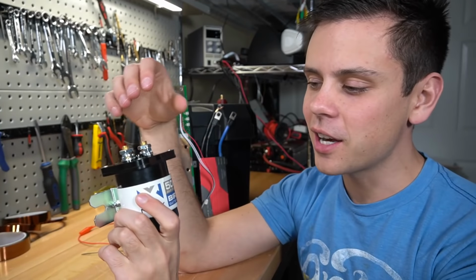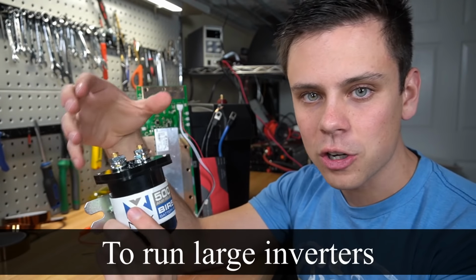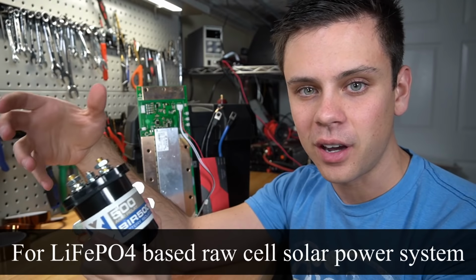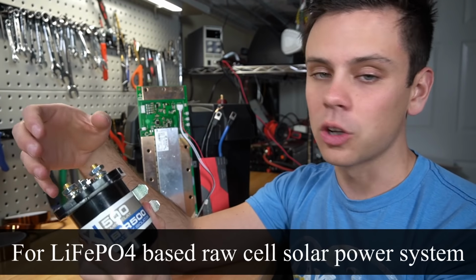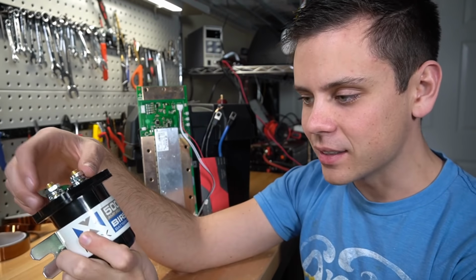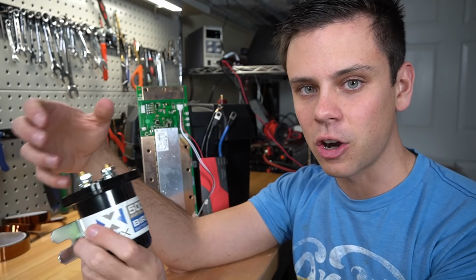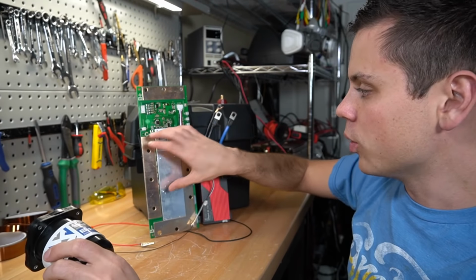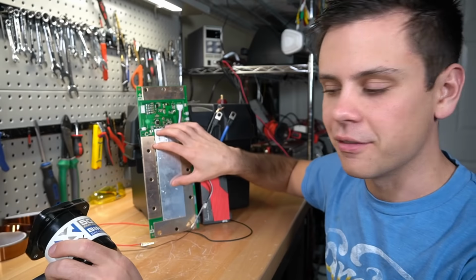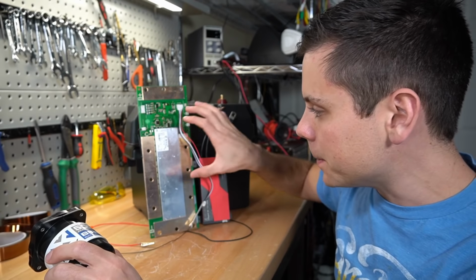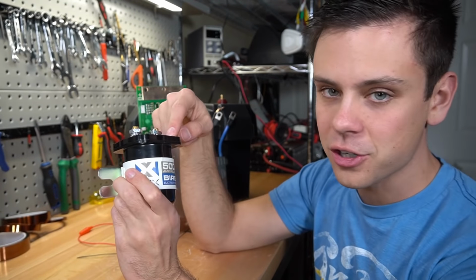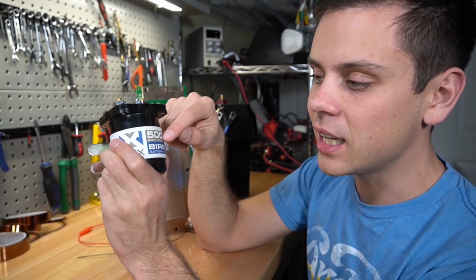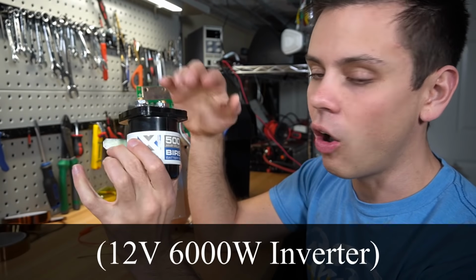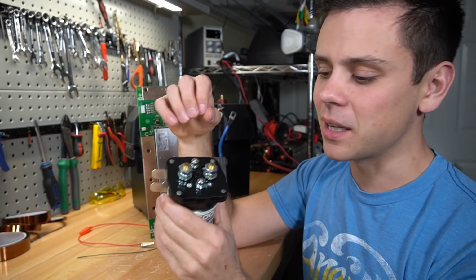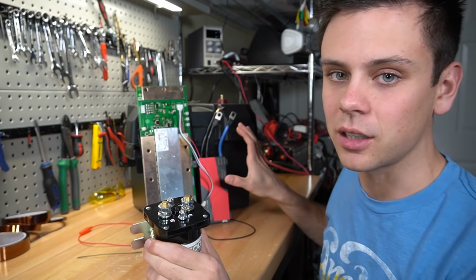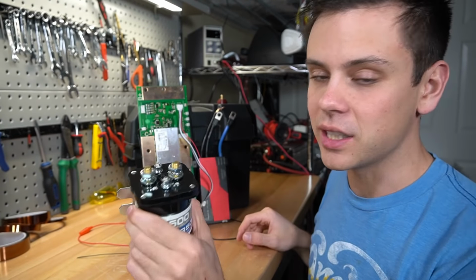Tonight we're going to learn how to use a relay to run large inverters for a lithium iron phosphate based raw cell solar power system. Instead of being limited to the current rating of your BMS, which is typically 100 or 150 amps, we're going to use the BMS to trigger a 500 amp relay so we can run continuous 500 amp loads all day long. These are very simple to use, and any BMS on the market can easily switch these on or off.